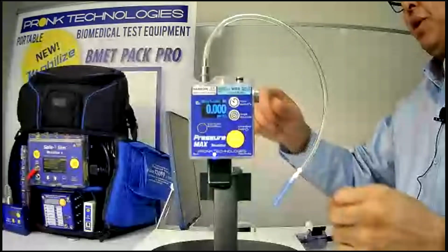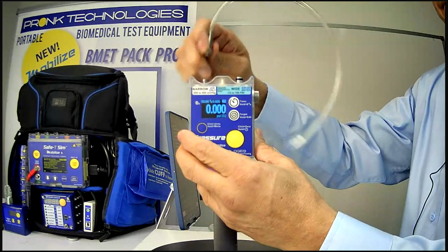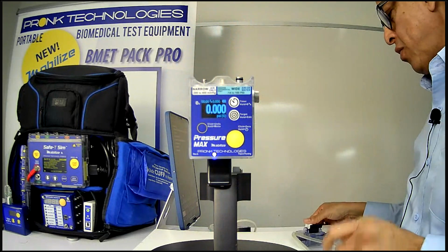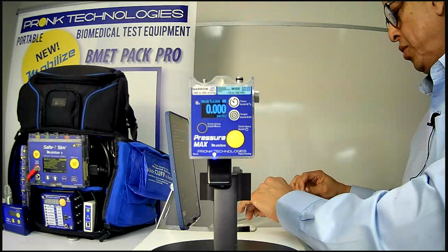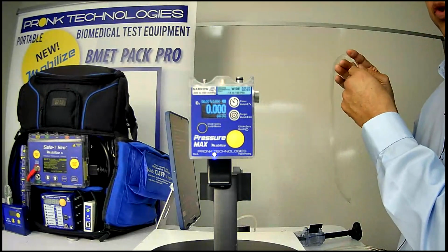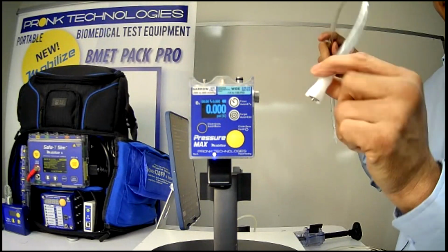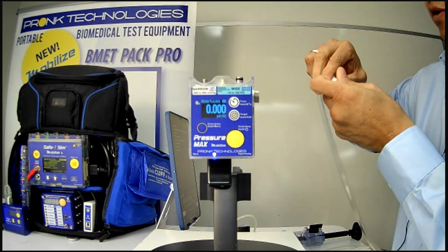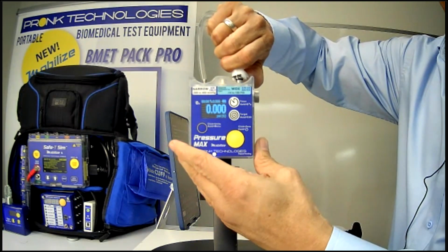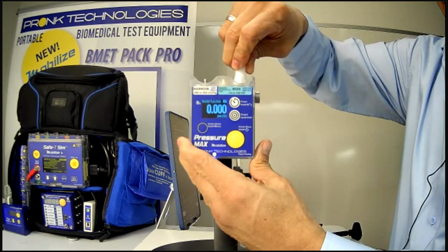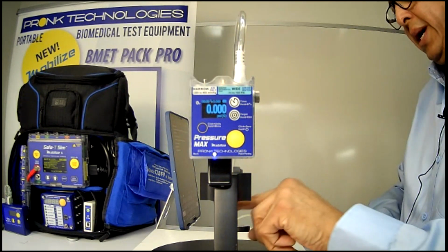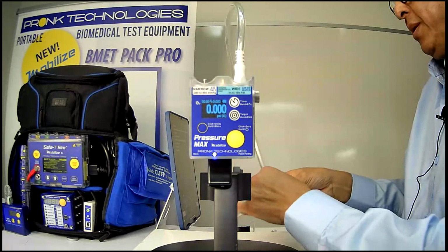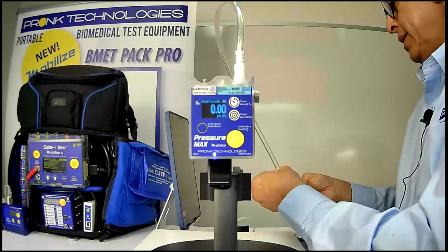Now the white port, as I mentioned, has a high pressure connector on it. We include with our unit a set of accessories you'll need to be able to utilize it, including a high pressure connector here, so we can be sure to measure pressure properly and safely. We'll just do a quick check on that. It locks right in there, so it's not going to come loose during a pressure measurement. So I'm going to connect this over here.